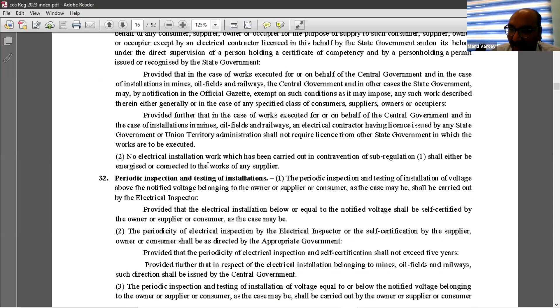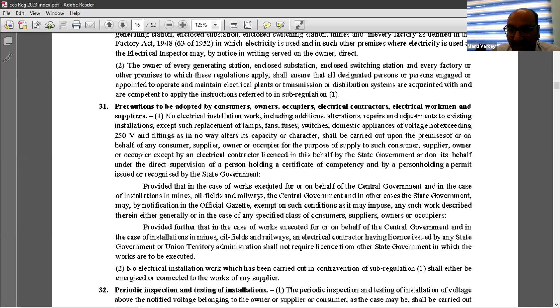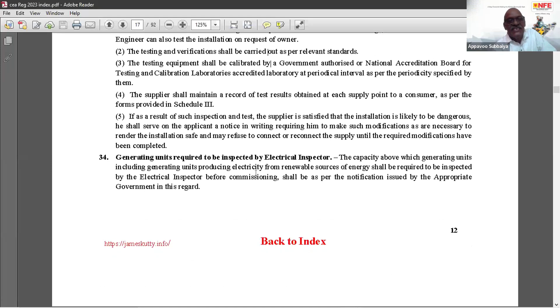After installation, this installation has to be inspected and verified, either by the consumer himself if it is below the notified voltage, or by an electrical inspector. So once the electrical inspector has given energization approval and the consumer has applied to the supplier for a supply, this regulation 33 comes into the picture. So under regulation 33, despite the certificates issued by the authorities, the supplier still has a provision to stop the connection, to refuse to connect. He can still refuse. That's what you want.